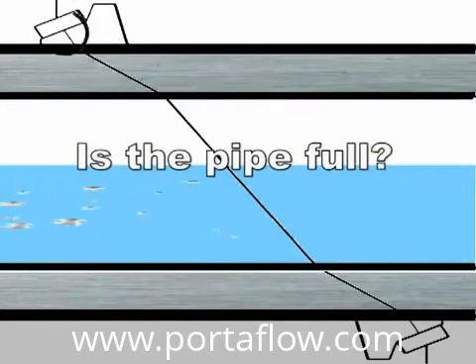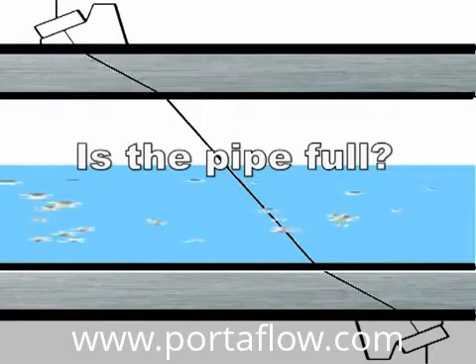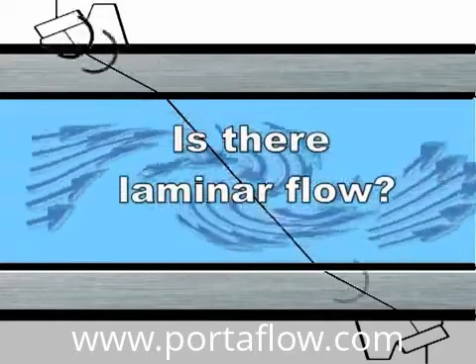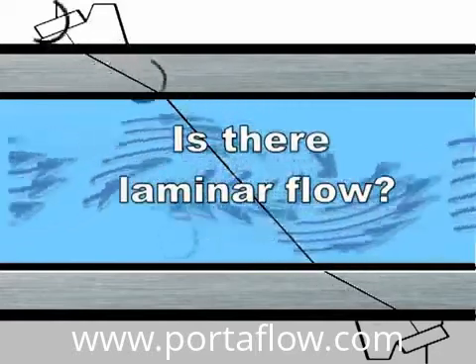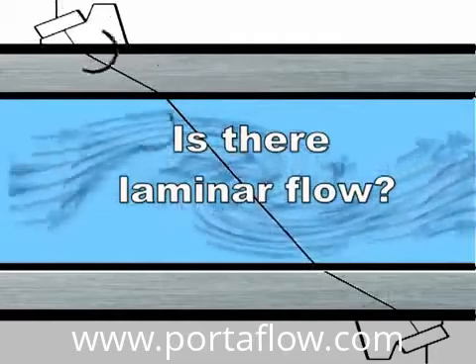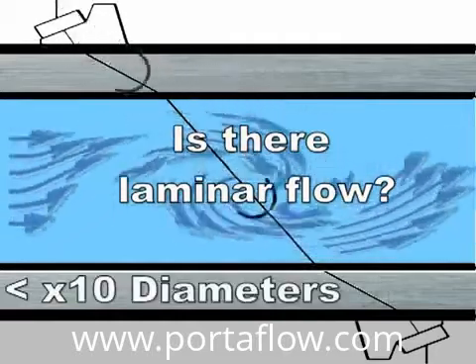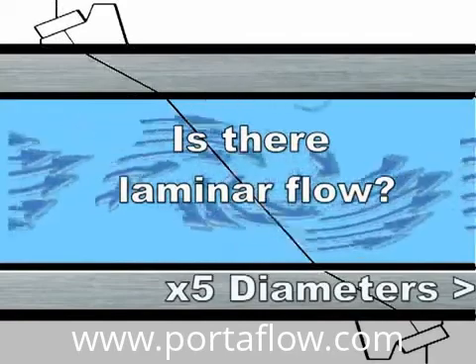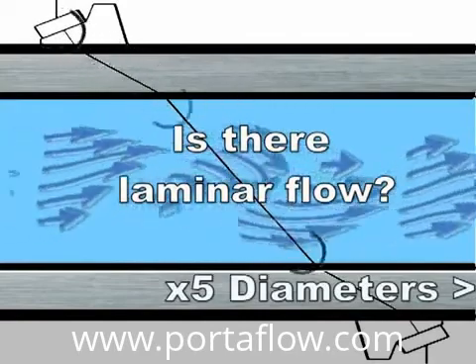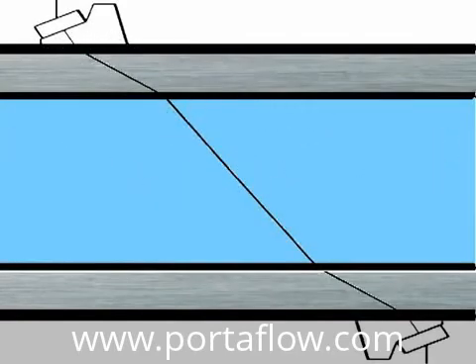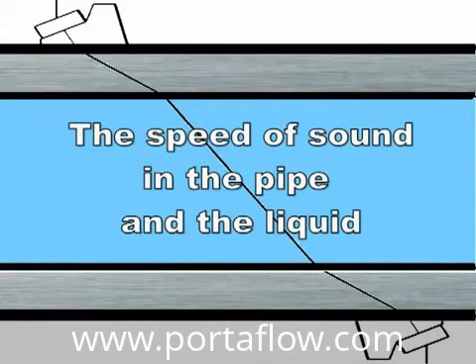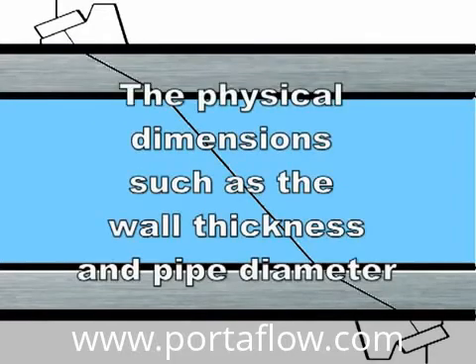Therefore we need to know: Is the pipe full? Excessive bubbles or particulates in the pipe will disperse the signal. Is there laminar flow? Because if it's very disturbed flow, again this will disperse the signal. Typically you'll have laminar flow when you have 10 diameters upstream and 5 diameters downstream from the flow meter clear of any obstructions. We need to know the speed of sound in the pipe and the liquid for the refraction angle calculation, as well as the physical dimensions such as the wall thickness and pipe diameter.